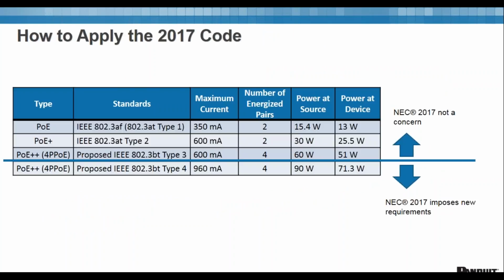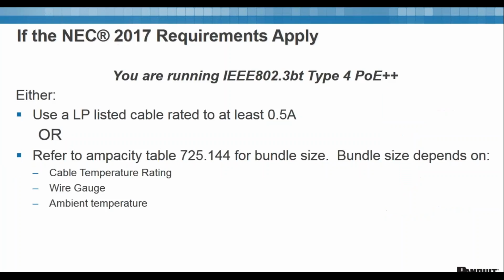So again, this is just breaking it down. One more way to show it is that with PoE++, the two new standards at the bottom: if you're above the line, the 2017 NEC is not a concern. If it's below that line, you have these new requirements. So if the requirements apply, you are running Type 4 PoE++.